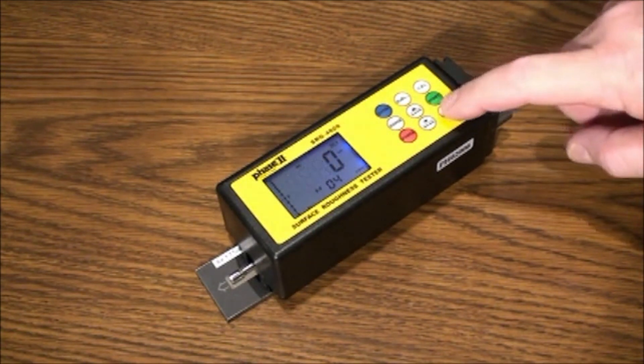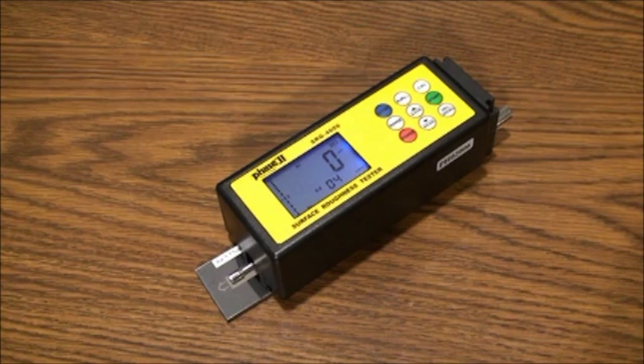Finally, after about 12 to 15 seconds of holding the menu button, the last menu selection is FAC. This is used to bring the unit back to its original factory-calibrated state using all defaults. It is recommended that you confer with a Phase II technician before attempting this procedure.